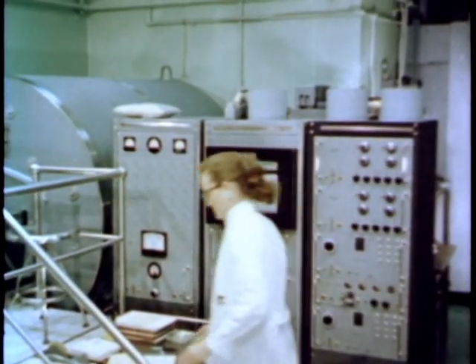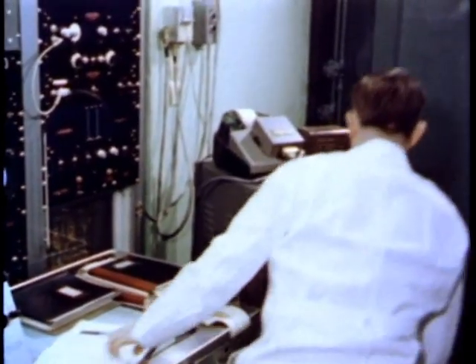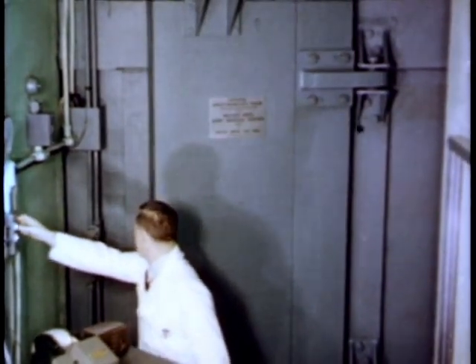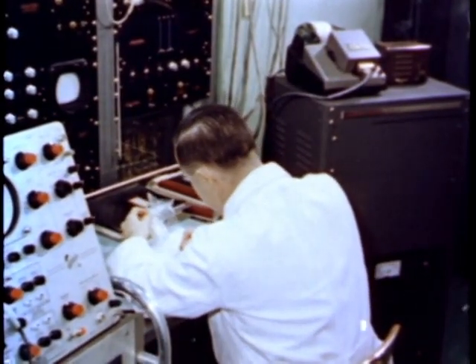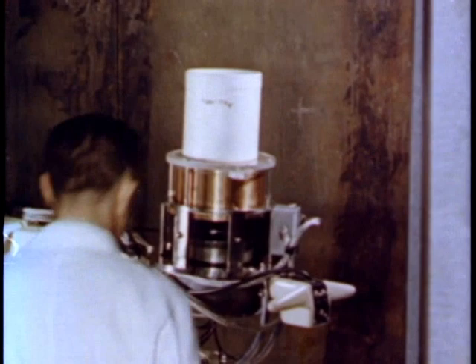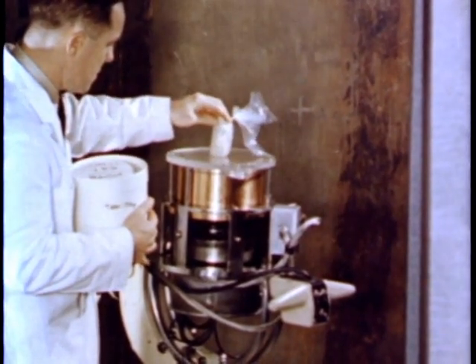To identify absolutely any particular isotope responsible for increased radioactivity in people, the iron room with its associated sodium iodide crystal and multi-channel analyzer was constructed. The iron room, erected from armor plates seven inches thick, measures about 12 by 6 by 7 feet. Overlapping plates cover all joints. Access is provided by a hydraulically operated door weighing approximately 8 tons. Constructed to provide shielding to reduce background, the 50-ton room permits measurement of low-level gamma activity.